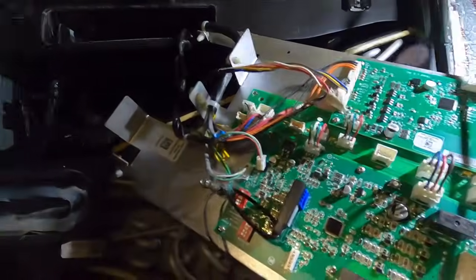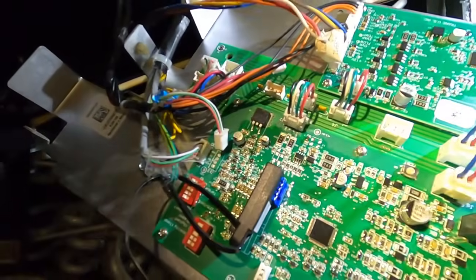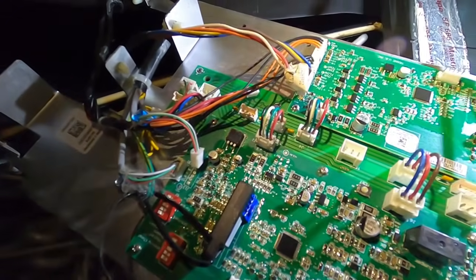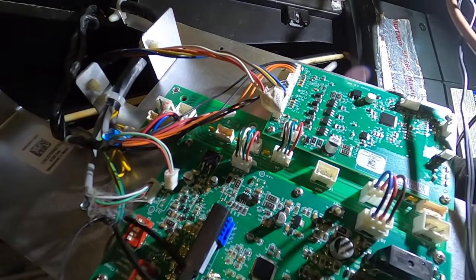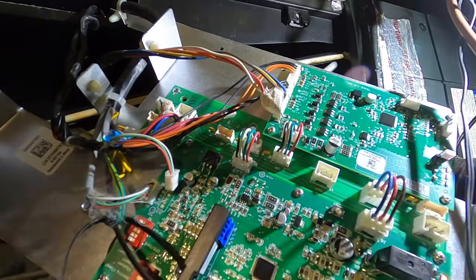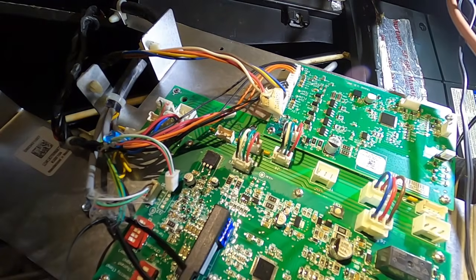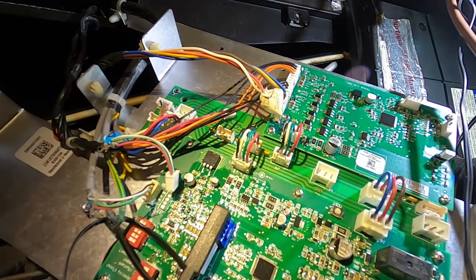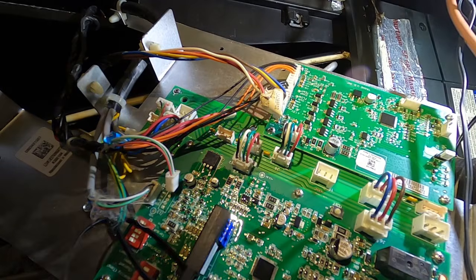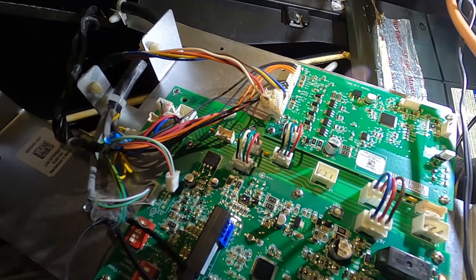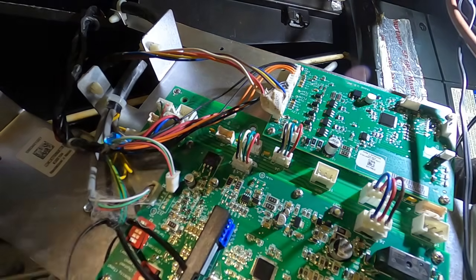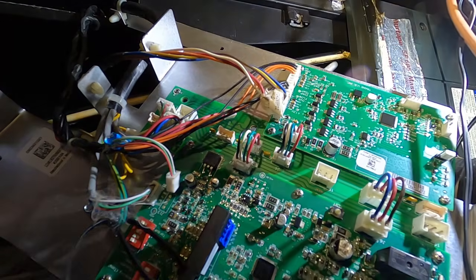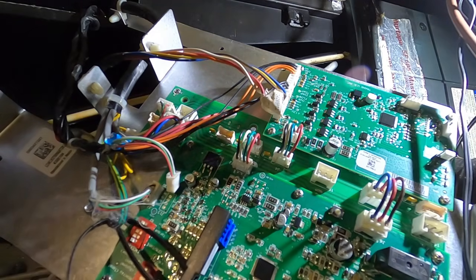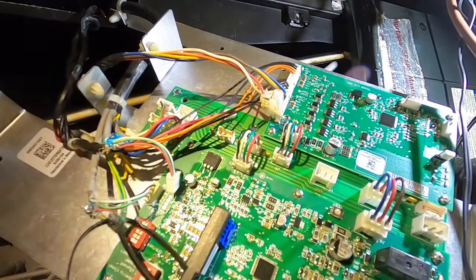And I usually just go by DC voltage. I said you can ohm them out, but DC voltage should be pretty much about the same if they're both good. If you get one that gives you like a 1.6 and another one that says 2.3 or 0.9, or way out of whack, then you know you got a bad sensor. Then you can confirm it by doing your ohms.